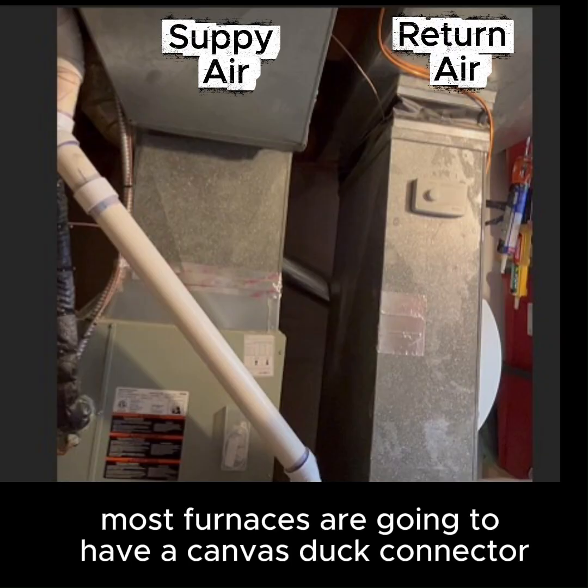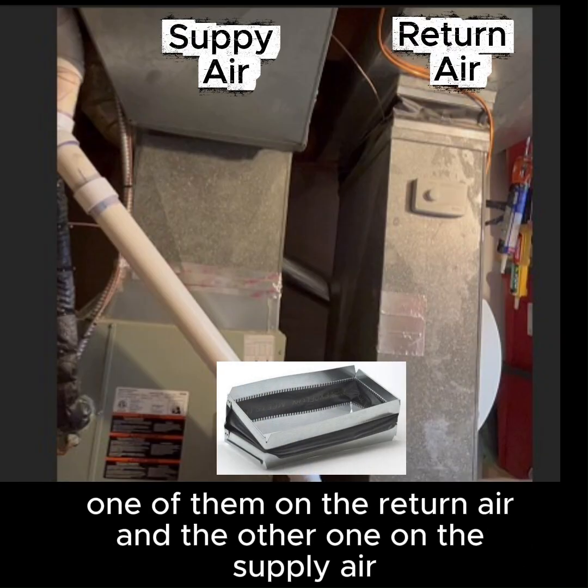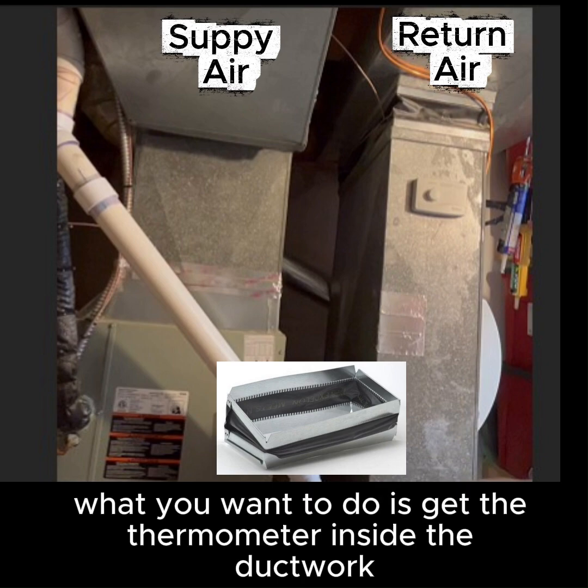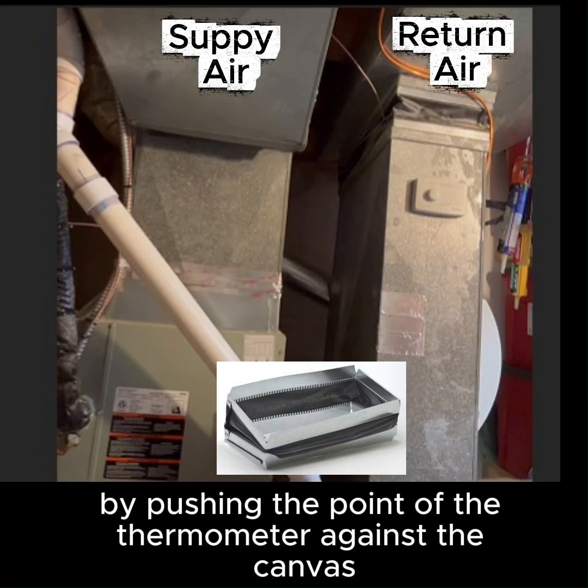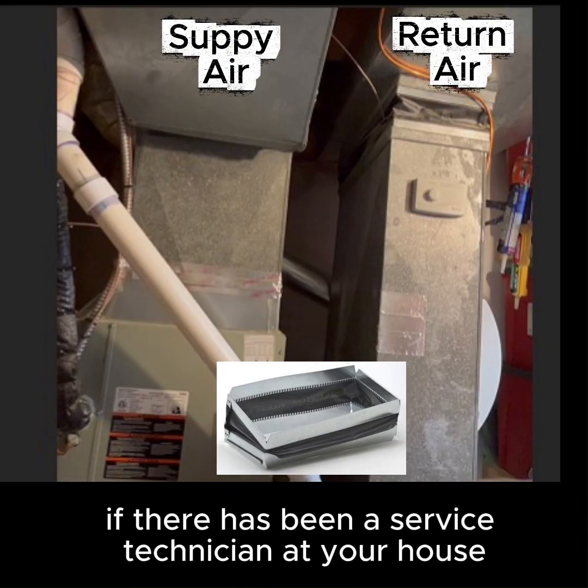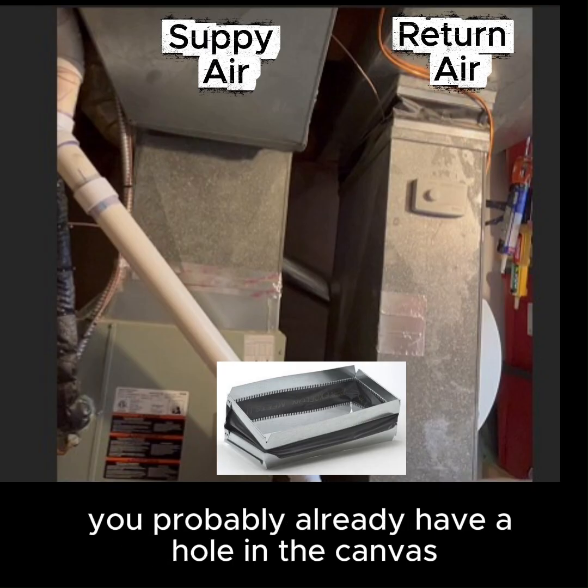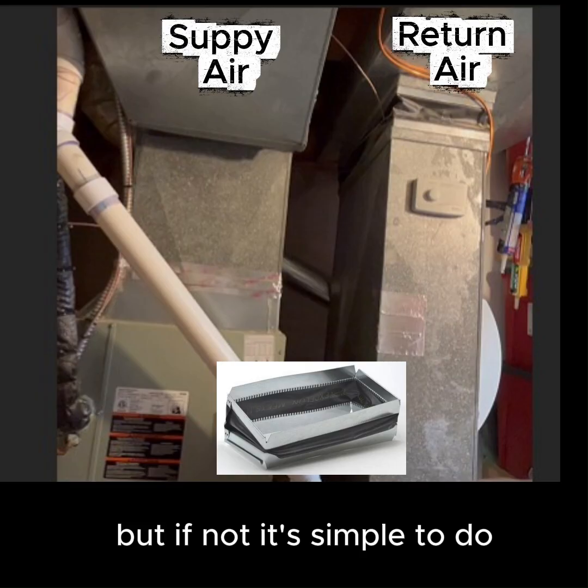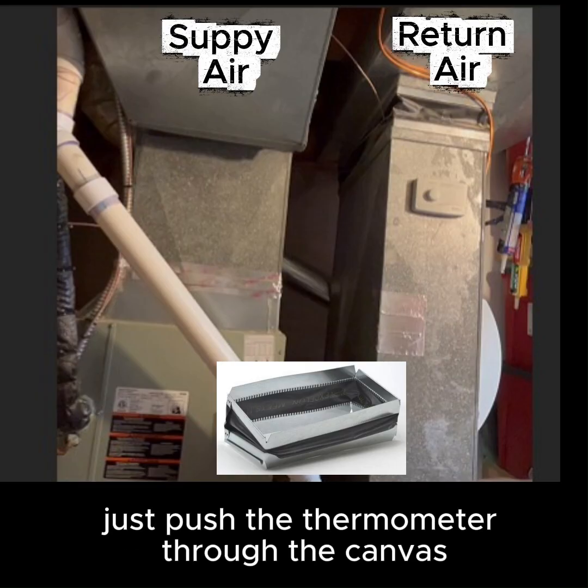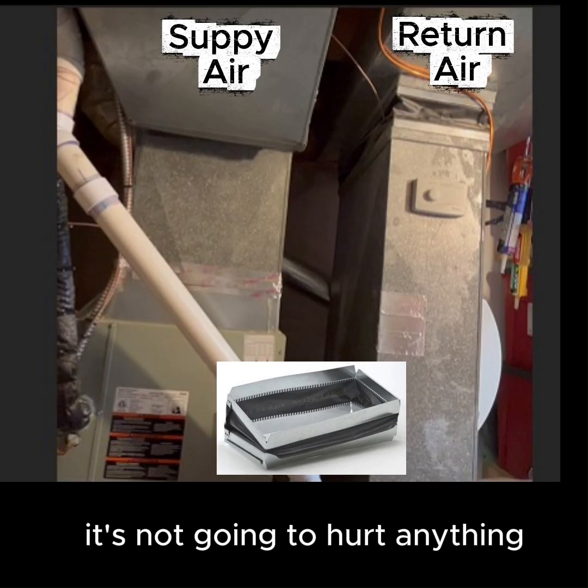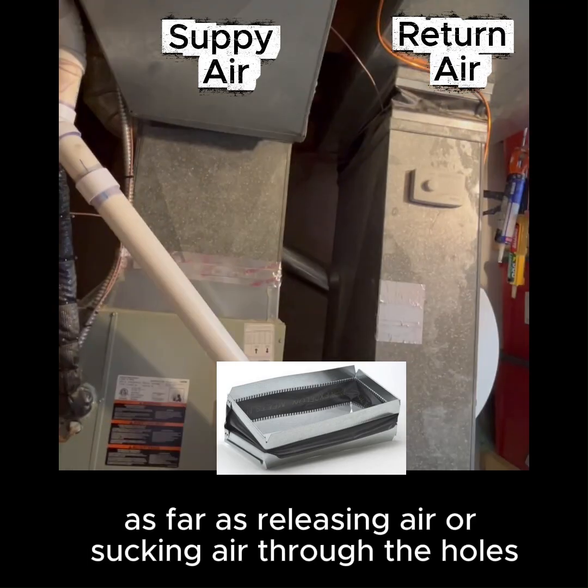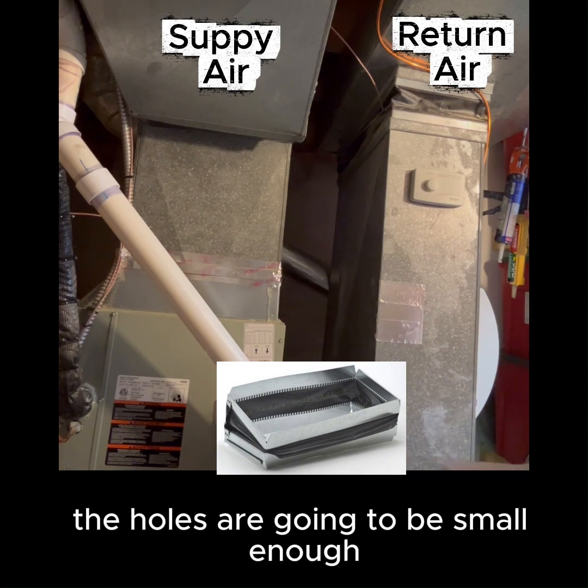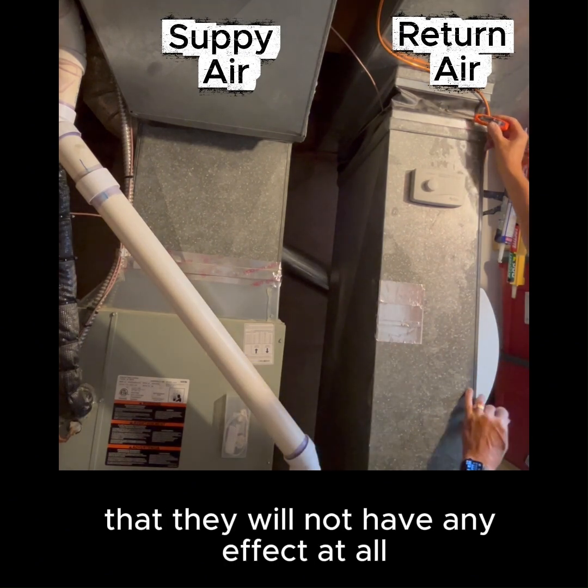Most furnaces are going to have a canvas duct connector, one on the return air and the other one on the supply air. What you want to do is get the thermometer inside the ductwork by pushing the point of the thermometer against the canvas. If there has been a service technician at your house, you probably already have a hole in the canvas. But if not, it's simple to do. Just push the thermometer through the canvas. It's not going to hurt anything as far as releasing air or sucking air through the holes. The holes are small enough that they will not have any effect at all.